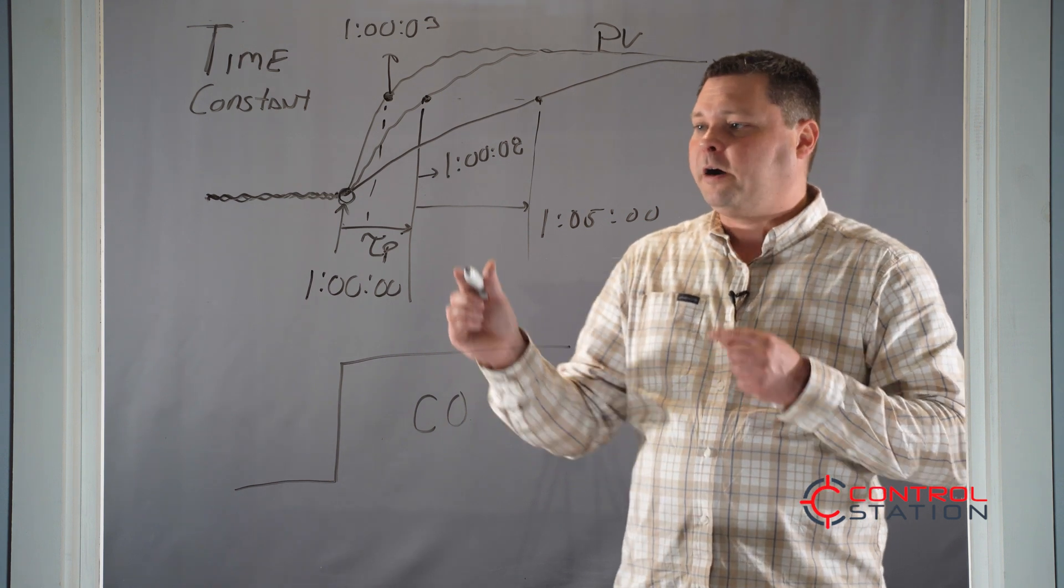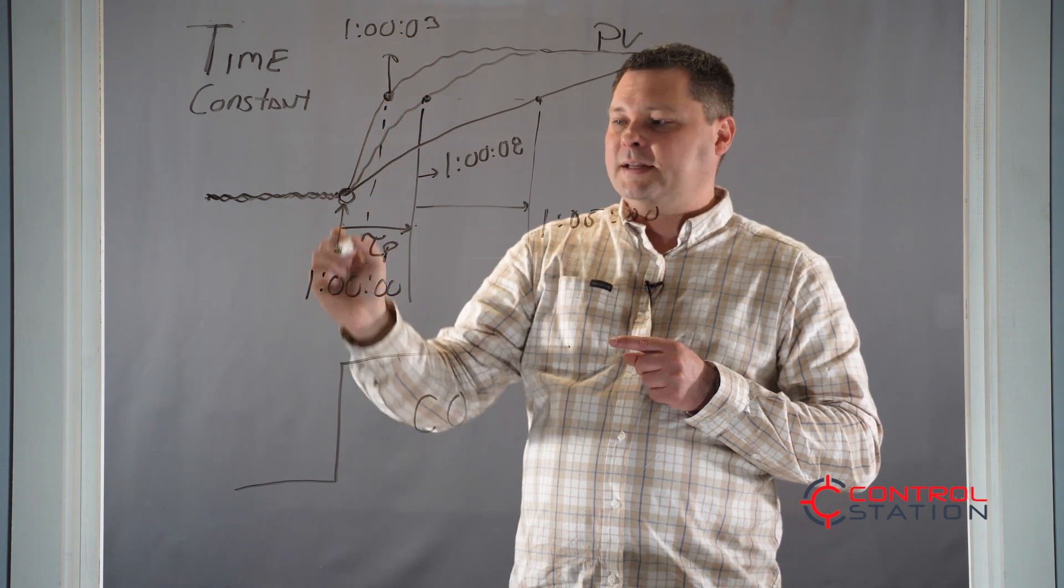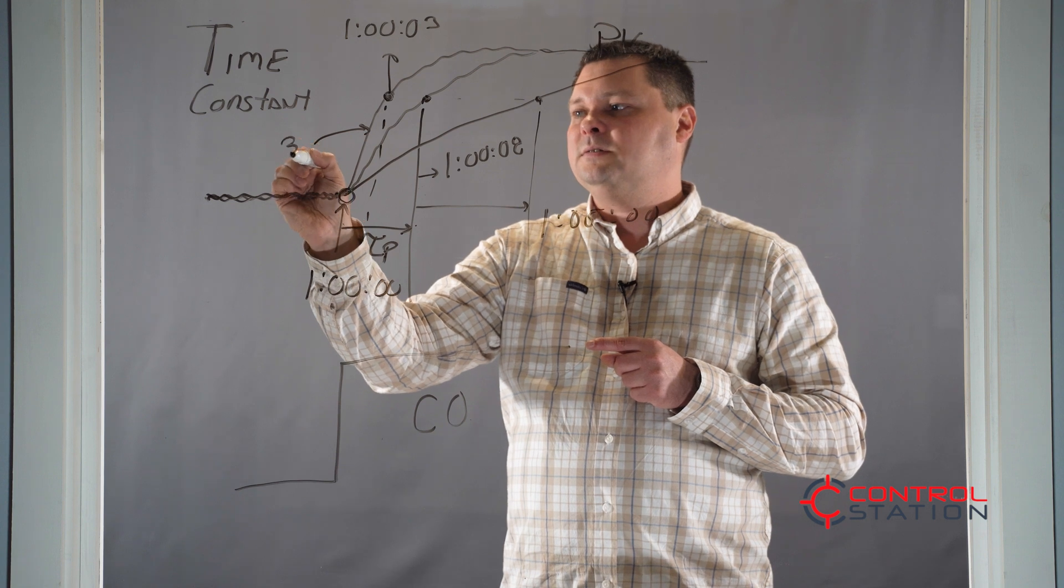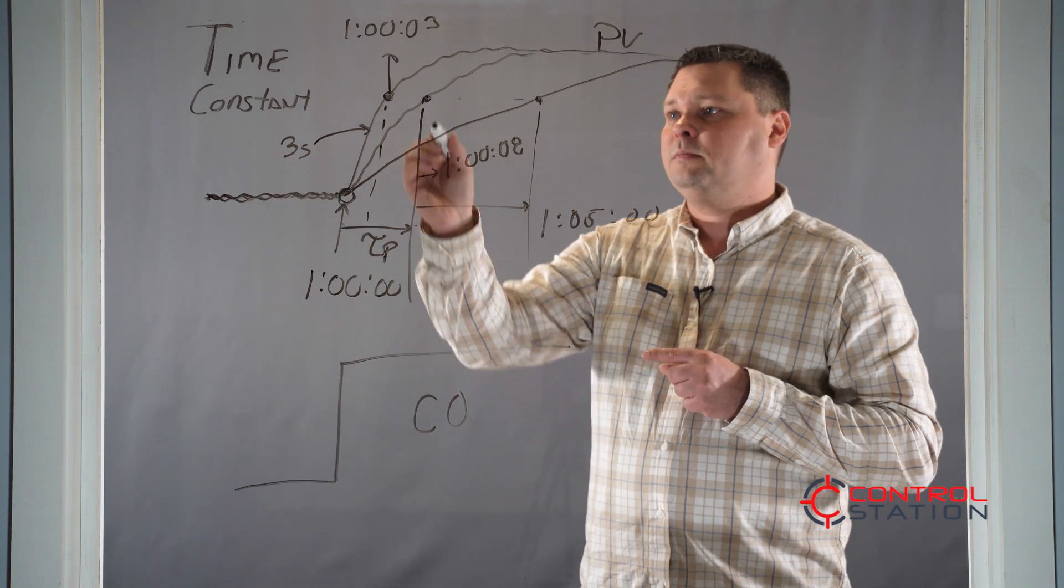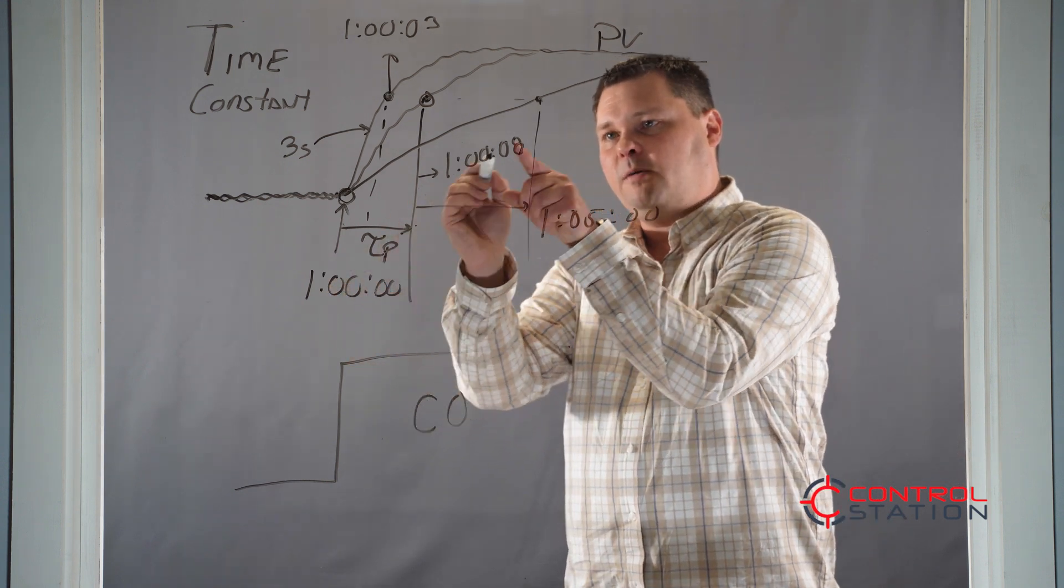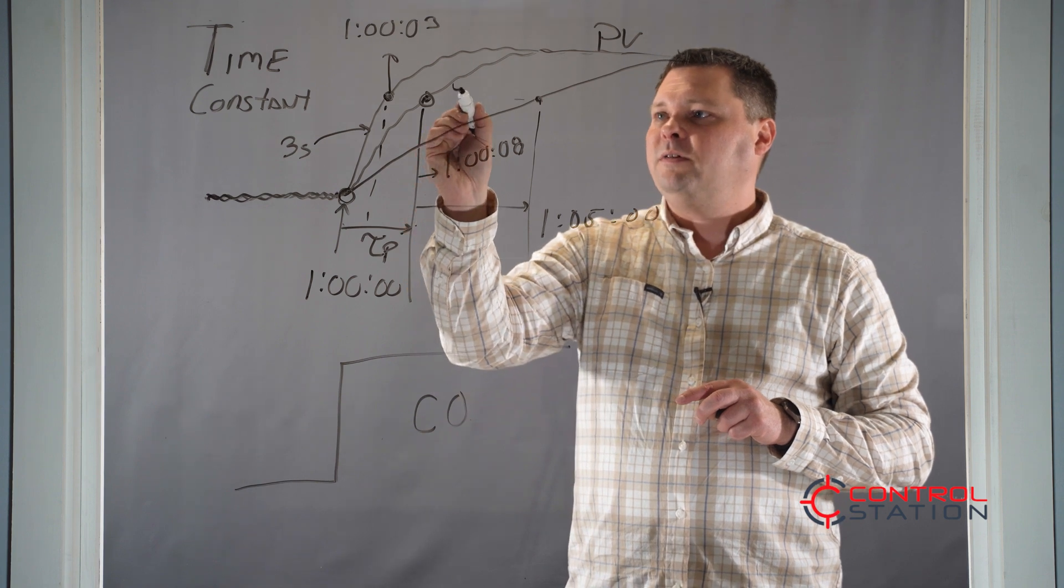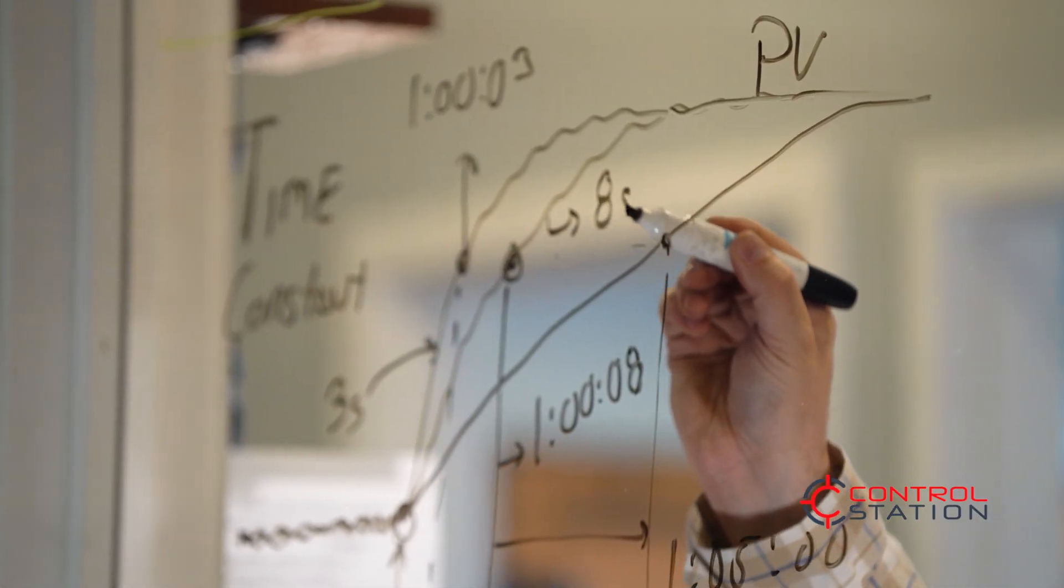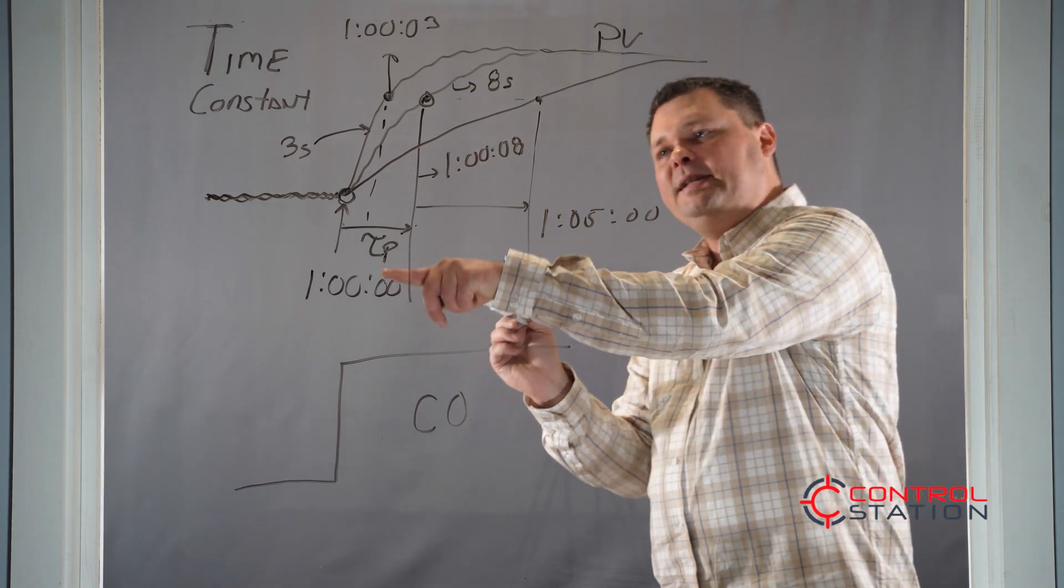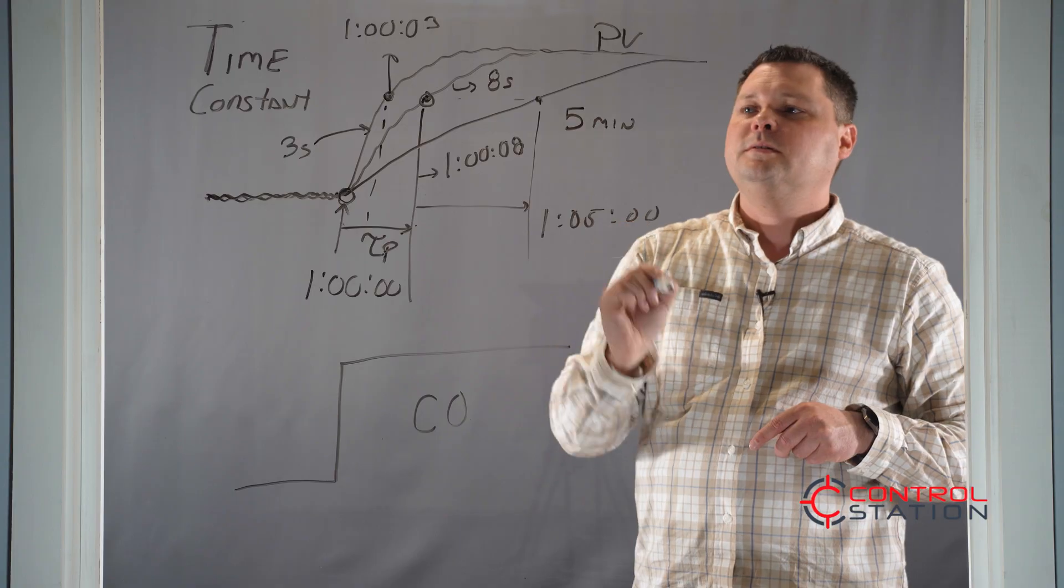So our time constant would be the difference. So the fastest loop, this was three seconds after this, so our time constant would be three seconds for this example. For this example, it took eight seconds to get there. So if this was zero, this was eight seconds, this would mean that your process time constant for this one is eight seconds. What about this very slow one? Well, it took five minutes to get there, so your time constant would be five minutes.